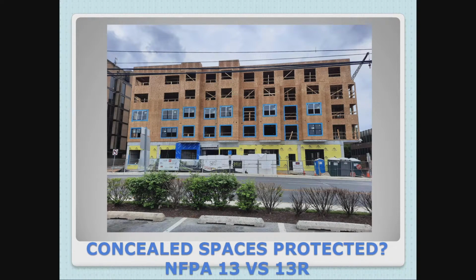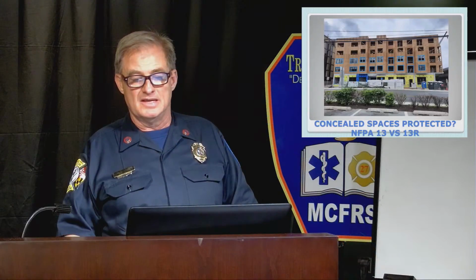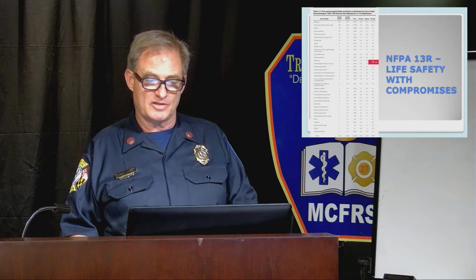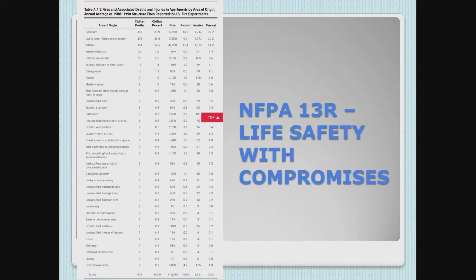There's no doubt. So what's the difference between an NFPA 13 system and an NFPA 13R system? The big difference is that with an NFPA 13R system, you do not have to sprinkler the concealed spaces. It is a life safety system. And what the code did years ago, and you can't fault them for this, because they were trying to design systems that would be economical so the building industry would stop fighting them on putting sprinklers in. And what they did, let me see if I can get my pointer to come up, is they looked at these numbers. And what these numbers represent are civilian deaths versus the civilian percentage of deaths in fires.